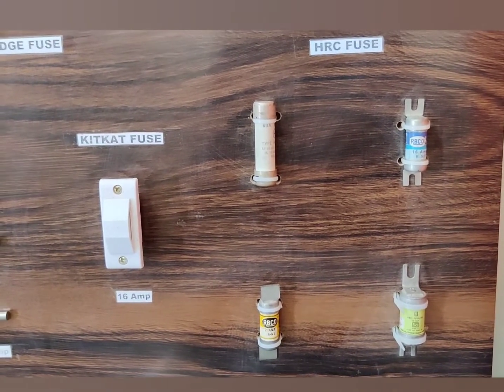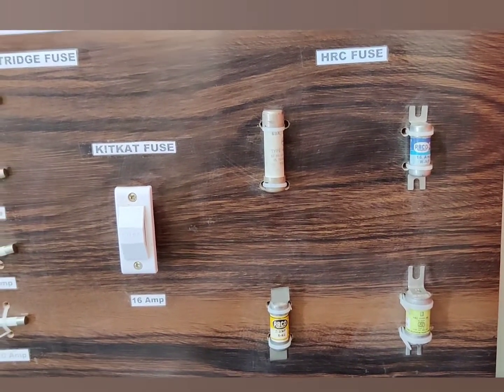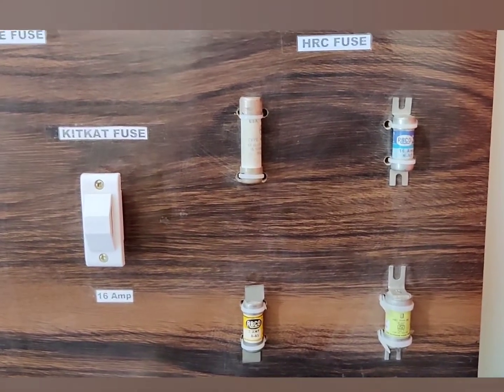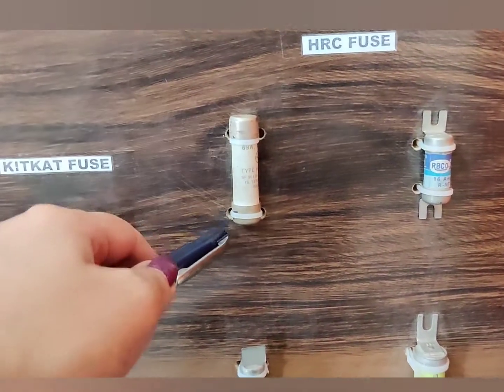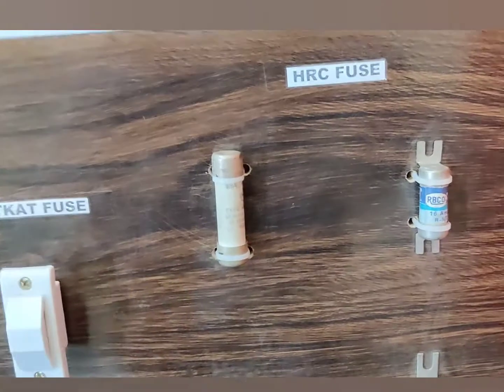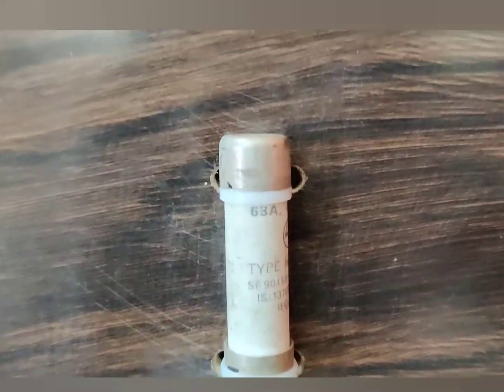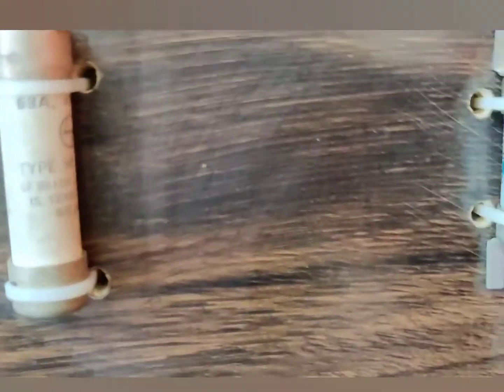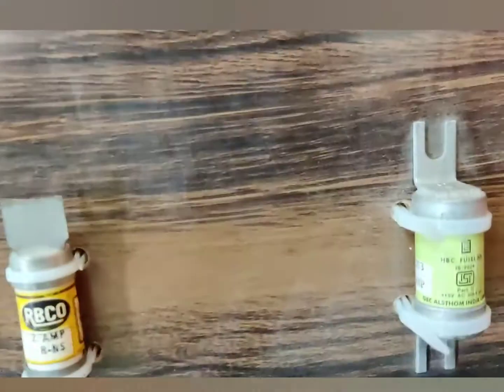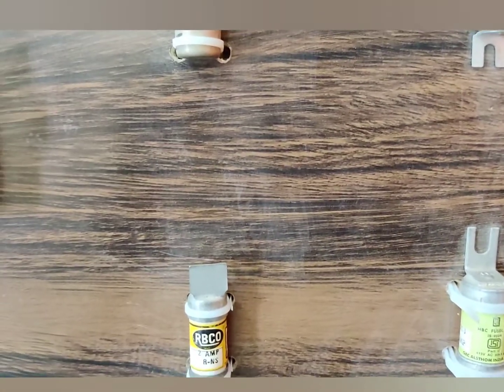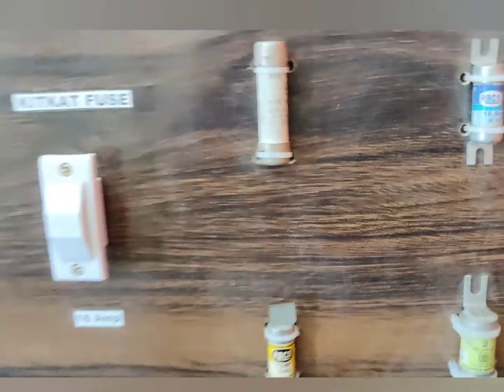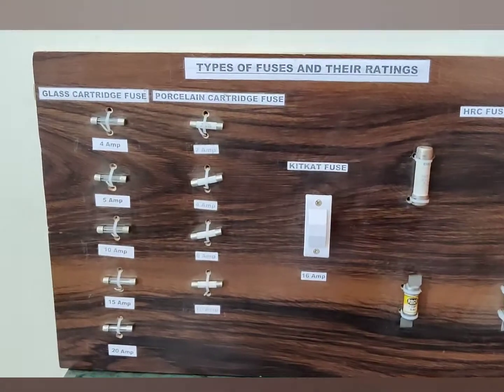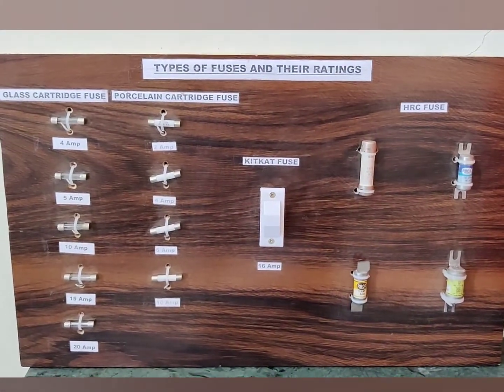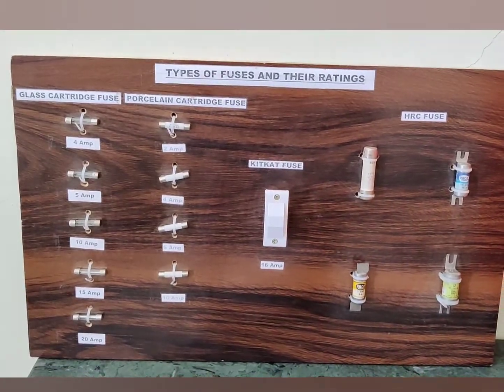HRC fuses basically consist of a heat resisting ceramic body which has these metallic end caps. So this entire body is heat resistant, and if you try to read out the current rating, 63 ampere, 16 ampere. So these are the fuses which have a higher rating when you compare them with the normal fuses. So these are the different types of fuses along with their rating.